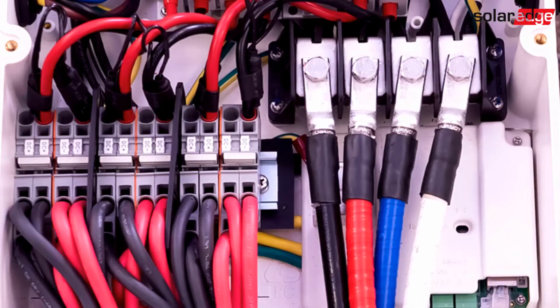With the connection unit cover removed, use a multimeter to test for AC voltage. Measure phase to phase, phase to neutral, and phase to ground. Ensure that all measurements are correct for your selected grid type. Finally, measure voltage neutral to ground. Your reading should be 0. If any voltage is found, be sure to inspect your AC installation.